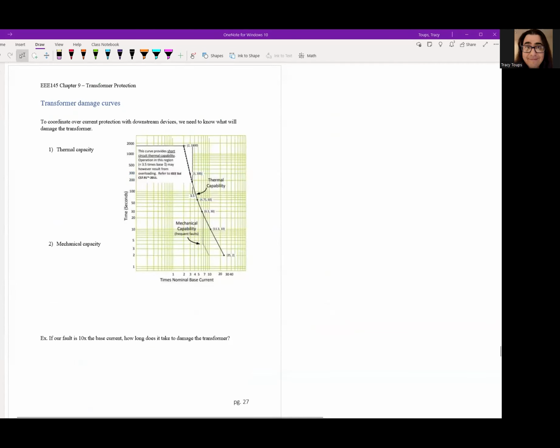Again, if the guy has a fuse, I would try to fight and get him to put a relay instead. Okay, so now we know where our 50-51 elements are going to be. They're going to be somewhere near the transformer. Now let's start talking about how to do coordination, because remember, every time we're doing a 51 element, we always have to talk about time curves, tap settings, and all that good stuff. Okay, so how does it work for a transformer?